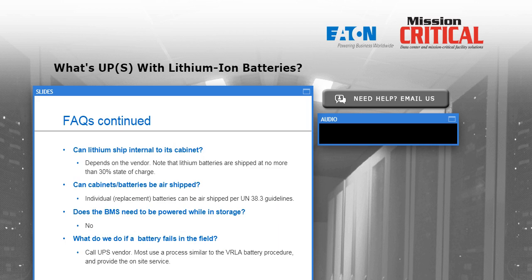Next slide: Can the lithium battery ship internal to the cabinet, pre-wired and ready to go? The answer is it depends on the vendor. Some vendors have passed the UL testing that allows the batteries to be shipped connected inside the cabinet with certain safety precautions. Other vendors are in process with that and will ship the cabinet empty with a pallet of batteries next to it. Keep in mind that generally they're going to be shipped at less than 30% state of charge regardless of how they're packaged.